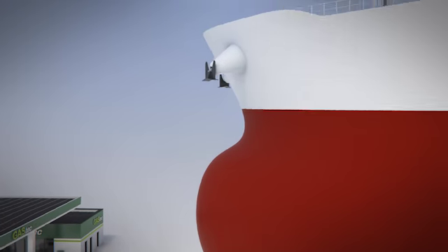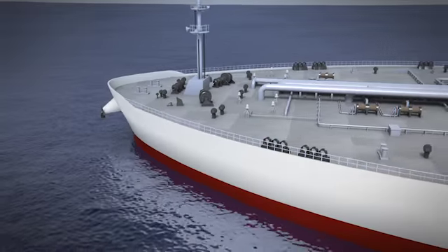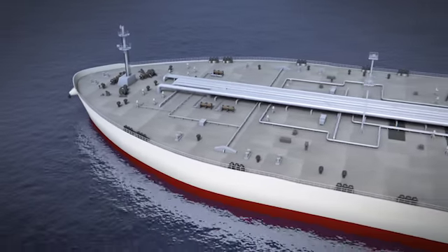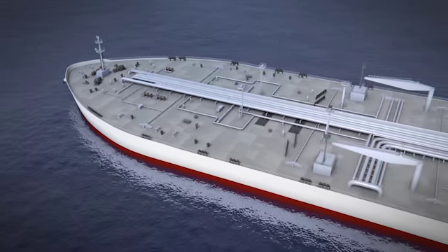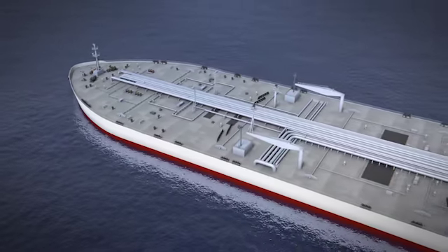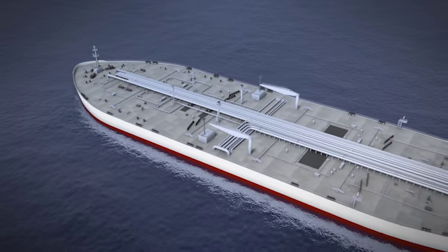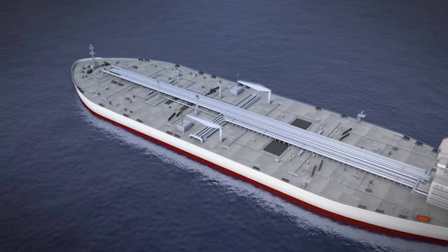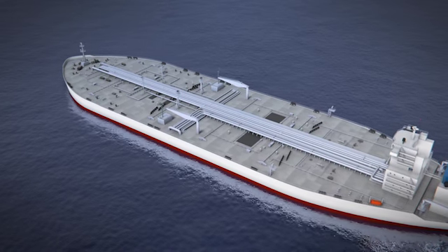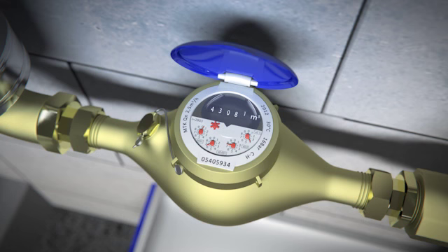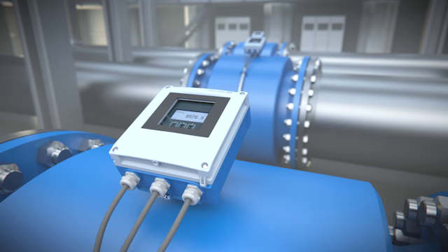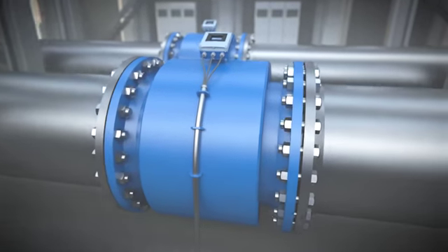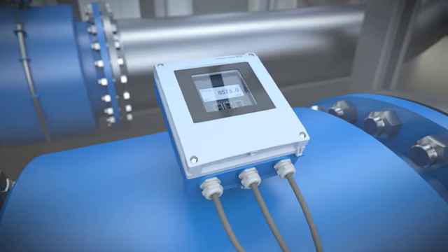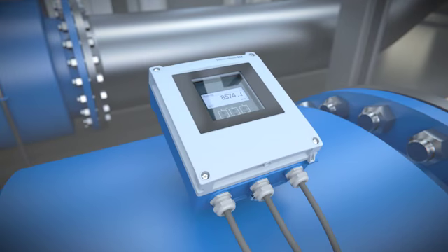For very small quantities, measurement inaccuracies may not cause losses significant enough for concern. But for oil tankers with huge capacities, the story is very different. When filling these tankers, even the tiniest measurement uncertainty can result in enormous shortfalls in end-of-year accounting, sometimes for the consumer and sometimes for the supplier. Therefore, all commercial measuring devices must meet certain legal requirements. But how can we know how accurate a flow meter really is? A calibration is the only way to answer this question definitively.